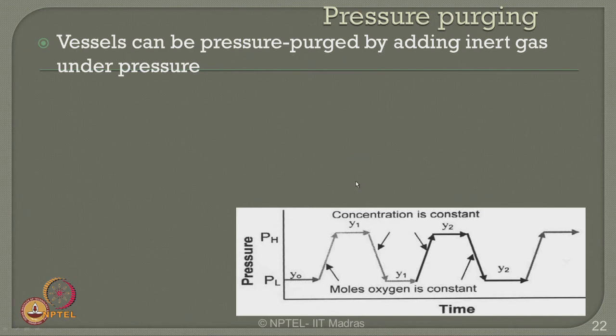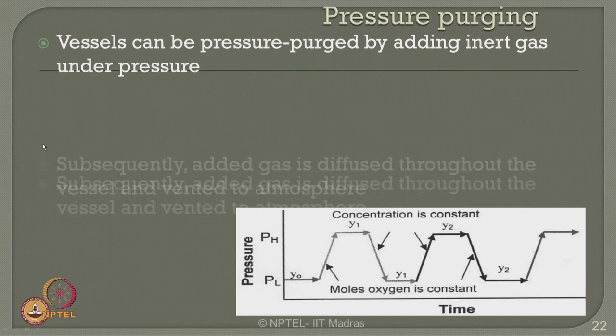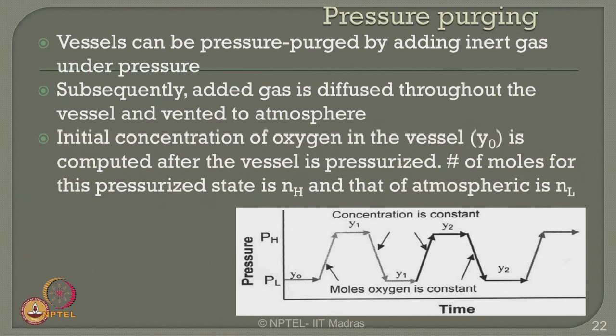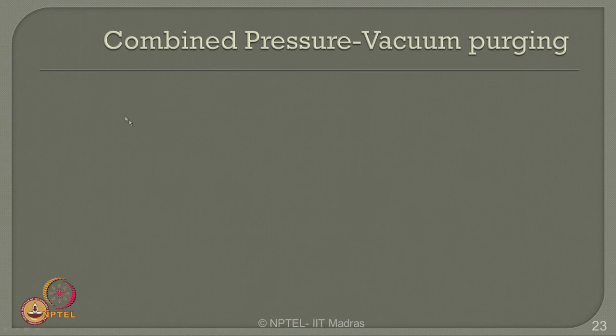One can also do pressure purging. In this case, from the lower pressure value the pressure is increased, with concentration changing from Y naught to Y1 and so on. While increasing pressure, moles of oxygen are kept constant. Vessels can be pressure purged by adding inert gas under pressure; subsequently the added gas diffuses throughout the vessel and is vented to atmosphere. The initial concentration of oxygen Y naught is computed after the vessel is pressurized. The number of moles for the pressurized state is N_H and for atmospheric is N_L.